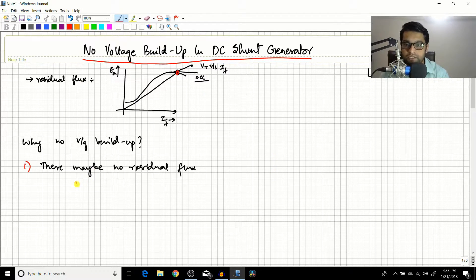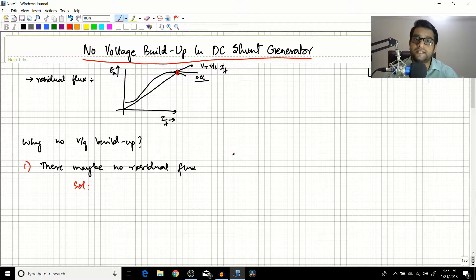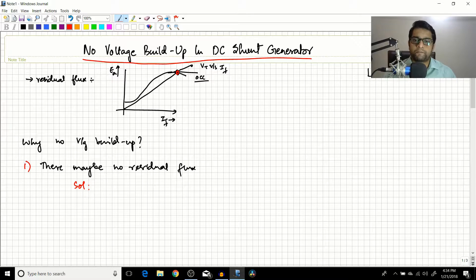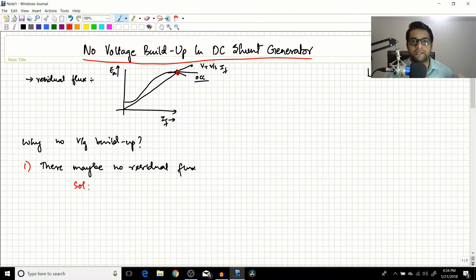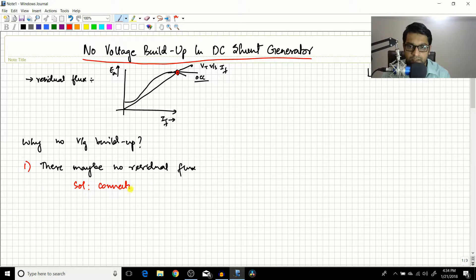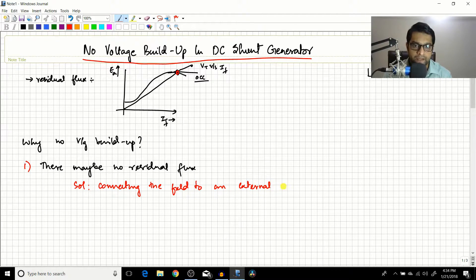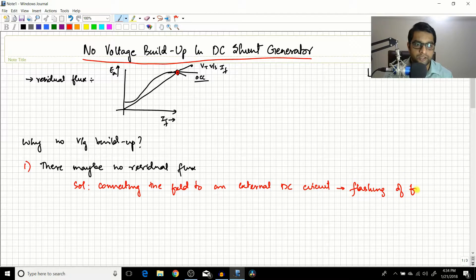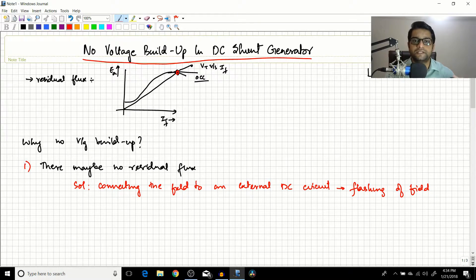The solution is to take the field circuit, connect it to an external DC supply, and let it develop a little bit of flux. When you remove it, some residual flux will remain. Connecting the field to an external DC circuit to restore flux is called the flashing of the field. This process establishes the residual flux needed for subsequent self-excited voltage buildup.